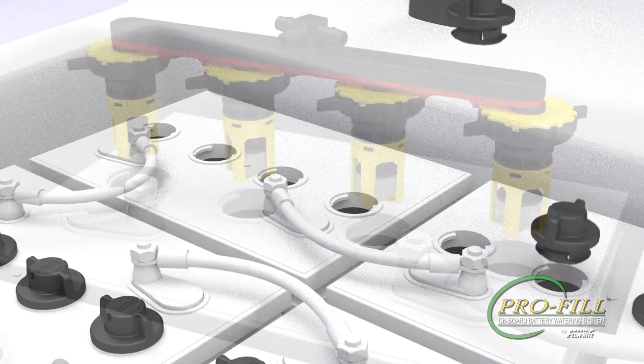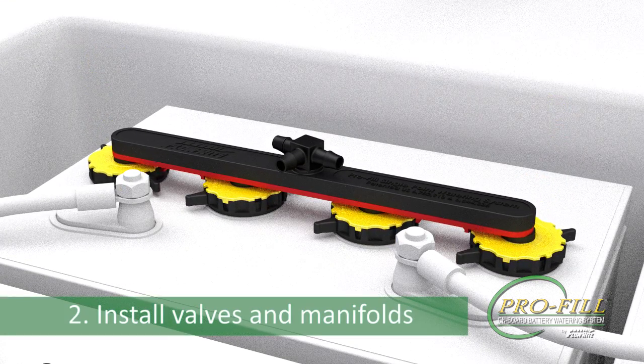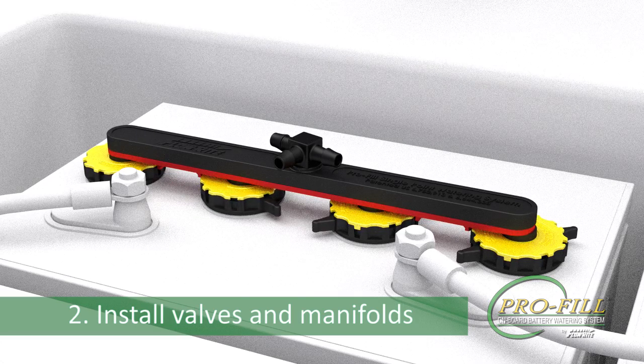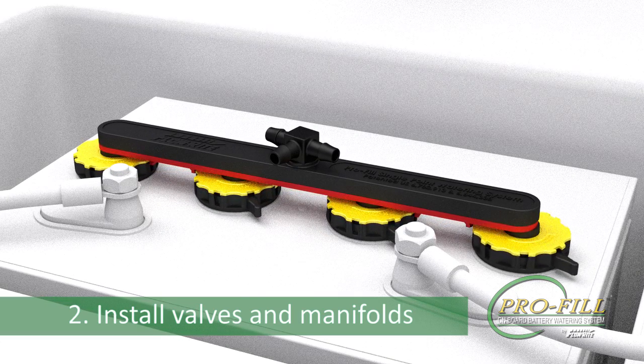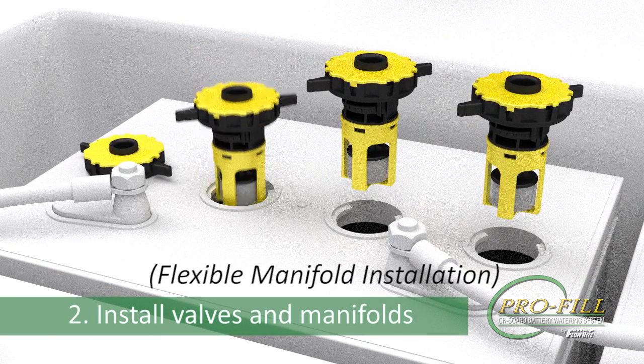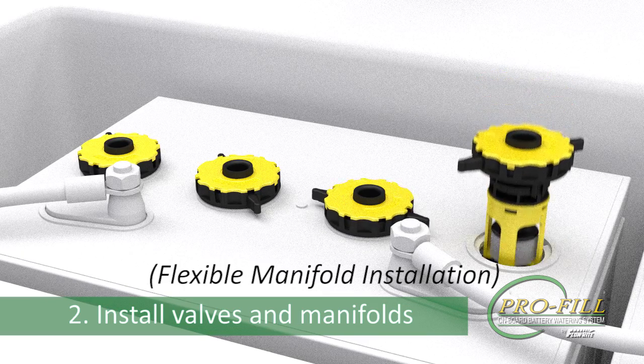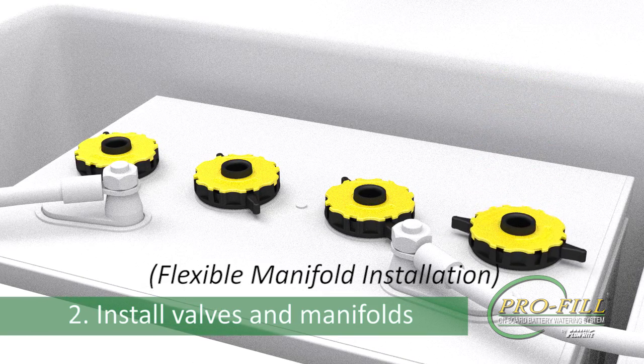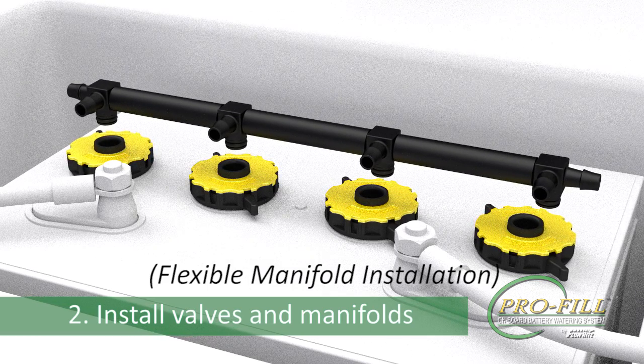Step 2: Insert a manifold valve assembly into each battery and secure the valves by turning each one a quarter turn clockwise. When installing a Pro-Fill kit that uses the flexible manifolds, first insert the valves and secure each one with a quarter turn clockwise. Next, attach the flexible manifold by inserting a swivel into each valve.